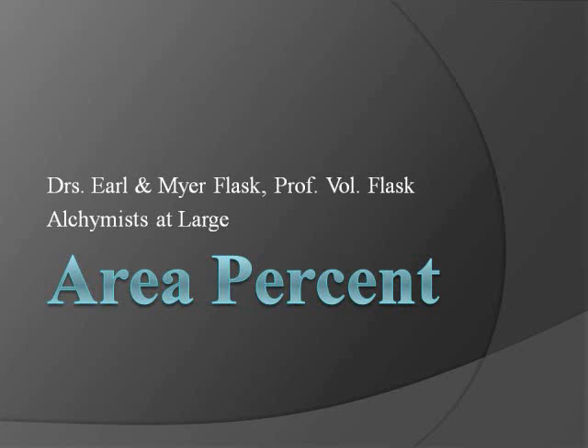The area percent calculation is one which determines the internal relationships between and among all of the peaks in a chromatogram consisting of more or less well-resolved peaks. This calculation can't be applied to gel permeation chromatograms or to other chromatograms in which the peaks are not well-resolved for reasons which we'll go into.